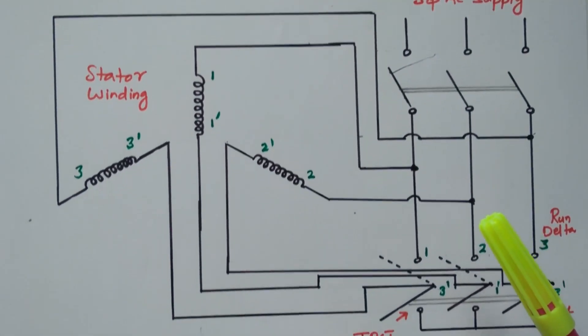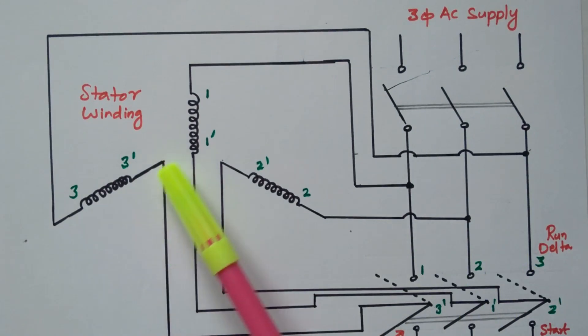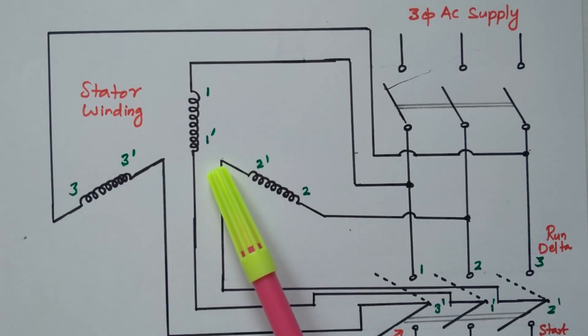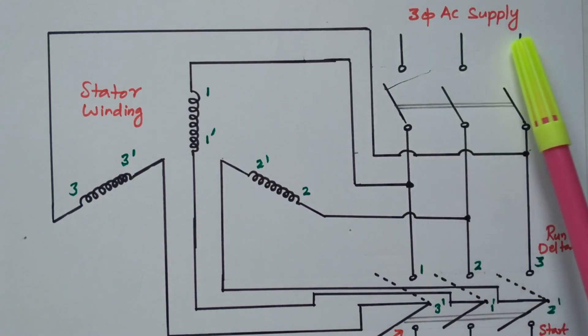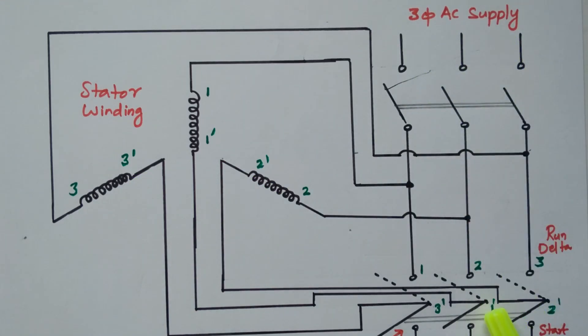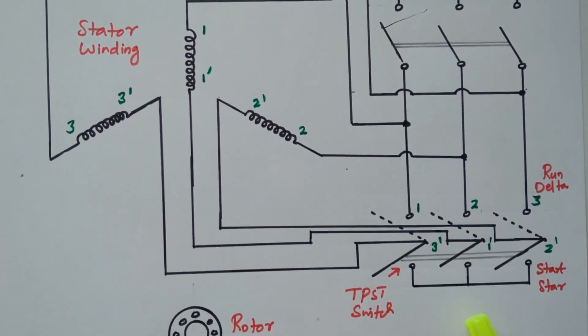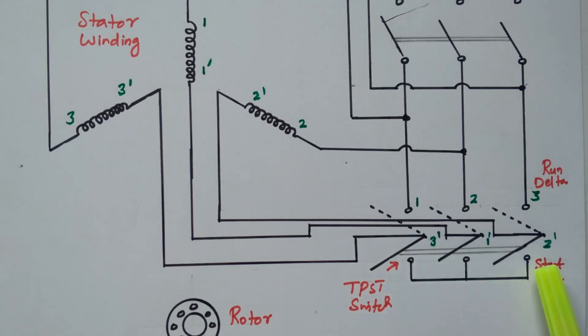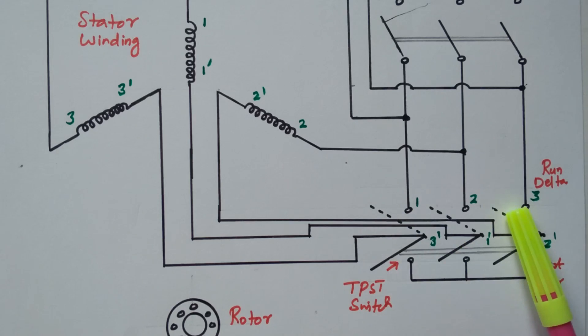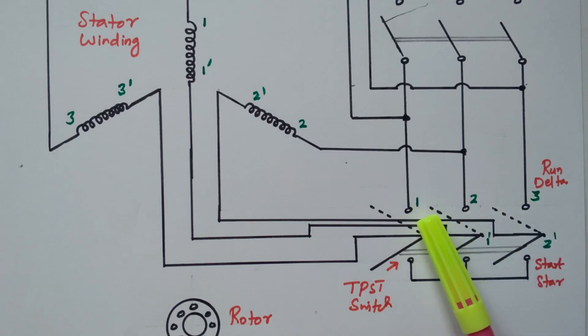Now refer the diagram. The stator winding is available here — stator winding phases: 1, 1-dash; 2, 2-dash; 3, 3-dash — three phases. Here the 3-phase AC supply is available, and a changeover switch, a TPST switch, is available. One side is connected with the star connection. If the switch is connected at the bottom end, the stator winding is connected in star — that is 1-dash, 2-dash, and 3-dash are connected. If the switch is connected at the upper end, it is a delta connection — that is winding portions 1, 2, 3 are connected.